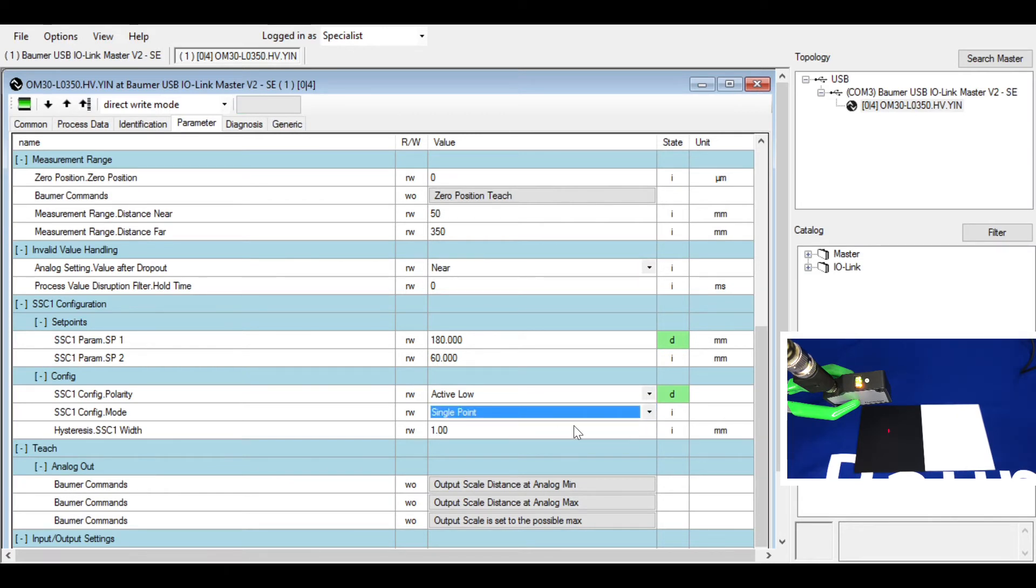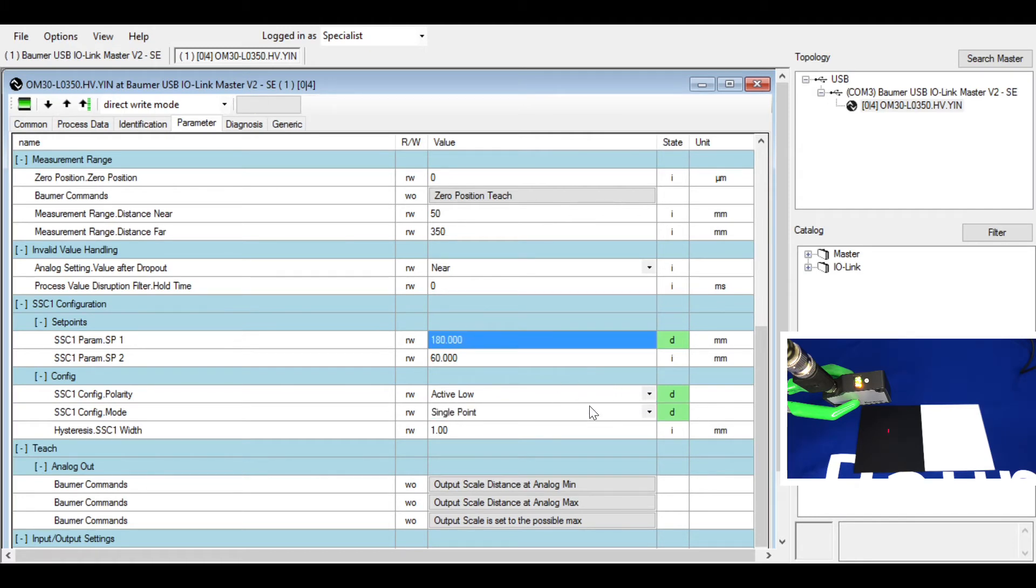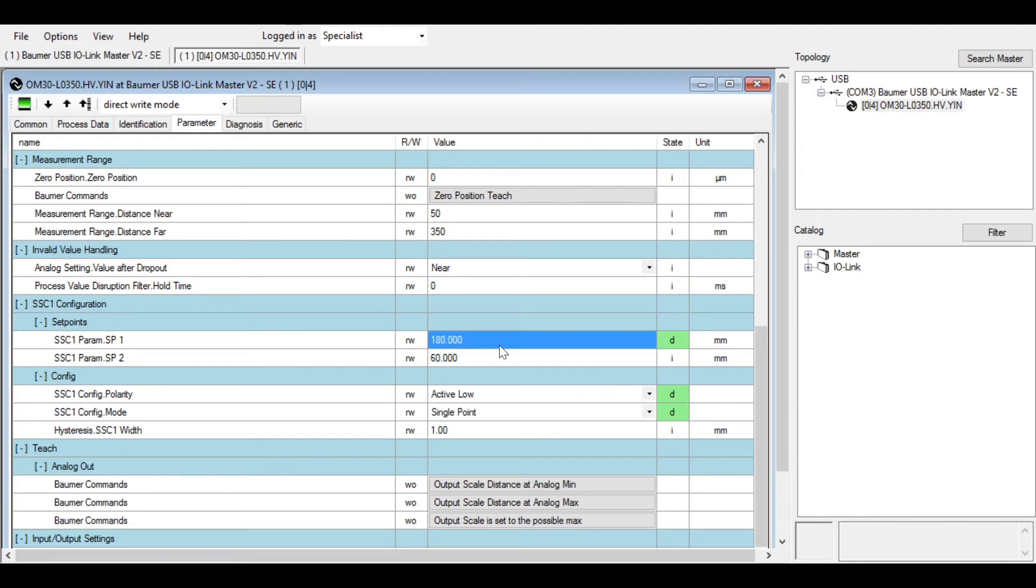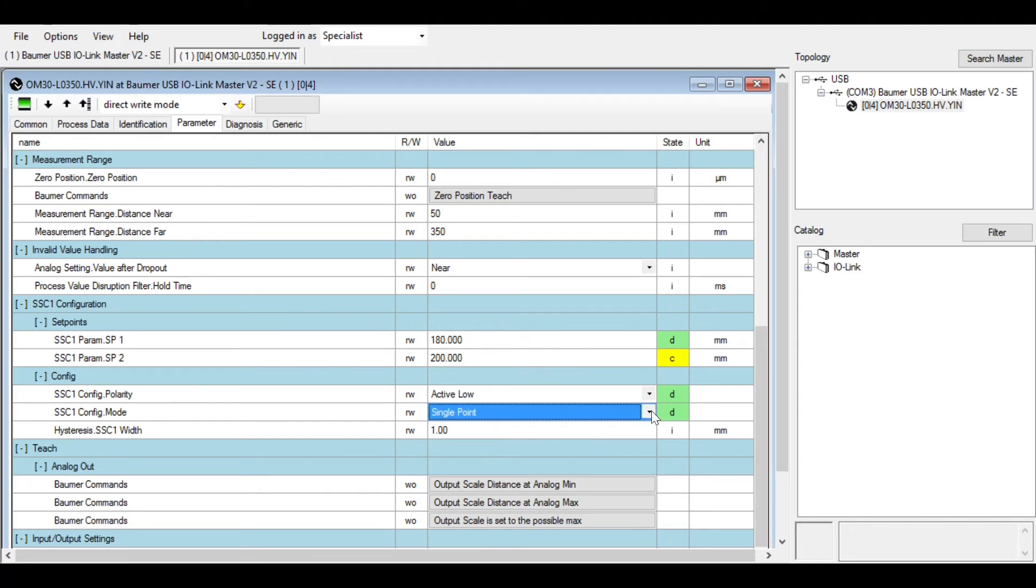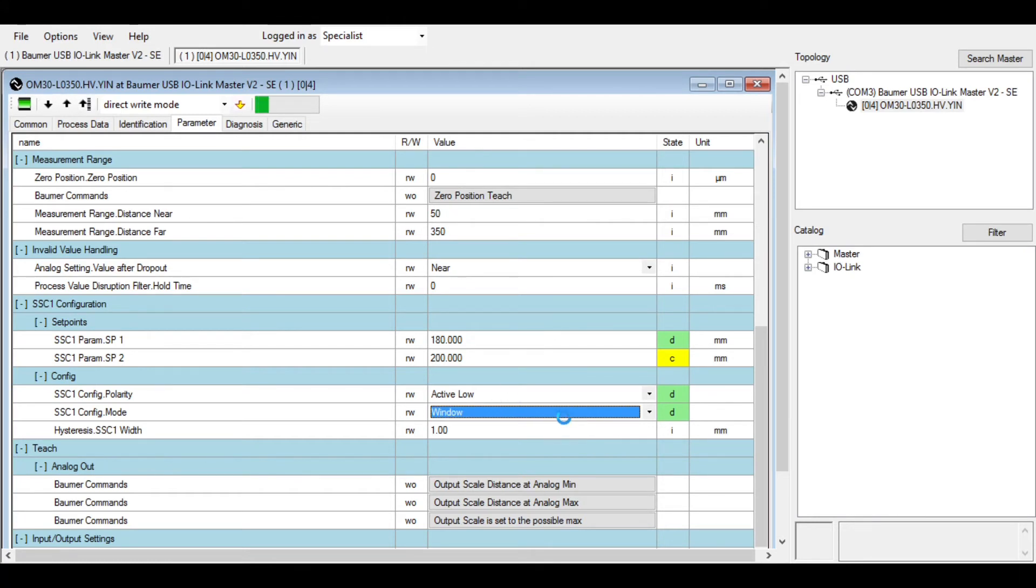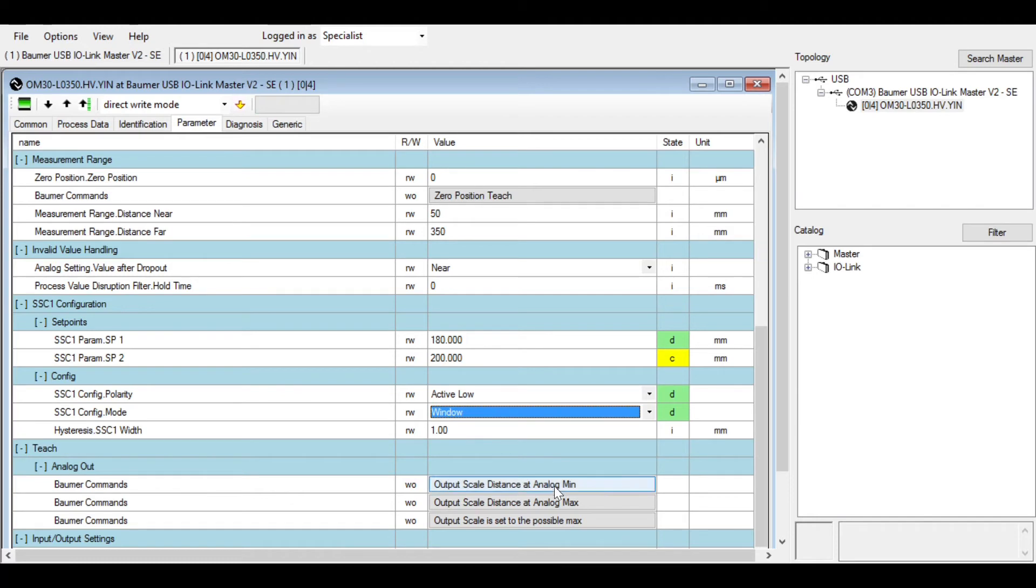The output will come on at that point. If you want it as window, you can say anywhere between, for example, 180 millimeters to 200 millimeters is okay, but outside of that range is no good. So change to window, the output will stay on between those two points and then turn off outside of those two points. You'll see that physically shortly.